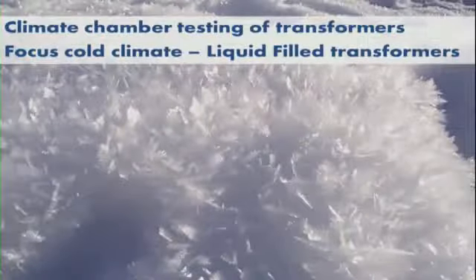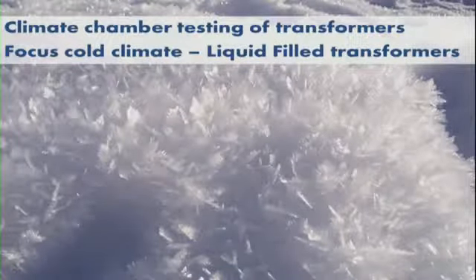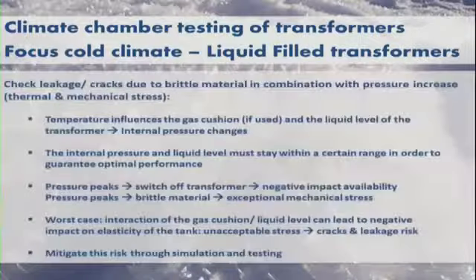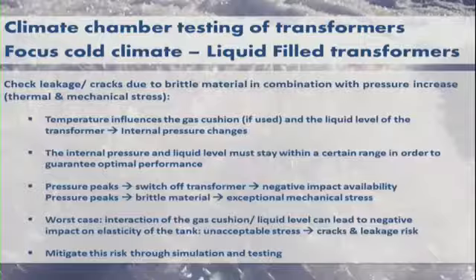The research, you can find it online. It's a shared paper between CG Power and OWI-Lab. So the first thing, leakage: what can happen if you have a liquid filled transformer, also with a gas cushion, for example. You cool it down, you can have under pressure. This is one thing we check. But if you put load on it, it will expand again, and that's why we check if there is any influence, if there are pressure peaks and so on.